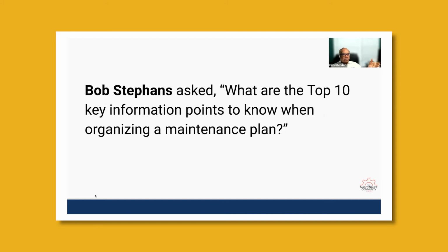Then I also need to know what I call nameplate data. Let's say take a motor, a 60 horsepower motor, or 100 horsepower motor, or 5 horsepower motor, that's not good enough. We need to have nameplate data because when you're ordering or you need to replace something, you need to have a frame size, a shaft size, the keyway, all those kinds of things are important. Those I call the nameplate data. So that data also should be in a CMMS system.